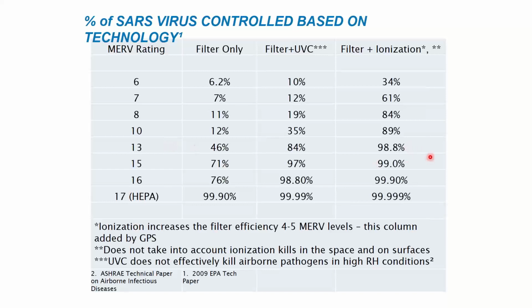I would take a Merv 13 with an ionizer at 98.8 and say that, for my purposes as a building operator and a homeowner, it's almost as good as a HEPA at 99.9. It's pretty much there as far as the grand schemes of horseshoes and hand grenades here. But the nice thing is a Merv 13 does not have very much pressure drop. The ionizer is going to make the filter work better because, once again, positive and negative attract. It makes things bigger, and once they're bigger, they're more likely to get stuck in the airflow. They're more likely, once they get back to the filter, to actually get stuck. So because I have lots of small things clumped together, they look like big things. So it's a way for my filter that can only catch big things to actually start catching some small things.